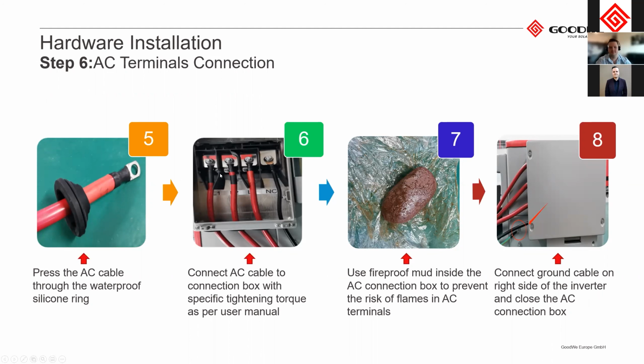As you can see, once this has been installed, you can use your fireproof putty, which is provided by us, to cover around the AC terminals or around the entry points of the cables, just to make sure that there is no risk of fire. Even if you're using a multi-core cable and you strip it around the bottom, you can also use this putty to put in between your conductors at the bottom, to make sure that, should anything happen and there's a hot connection, it won't melt down all the way in and cause an explosion with the three cables touching each other. And as you'll see, the ground terminal is here below.